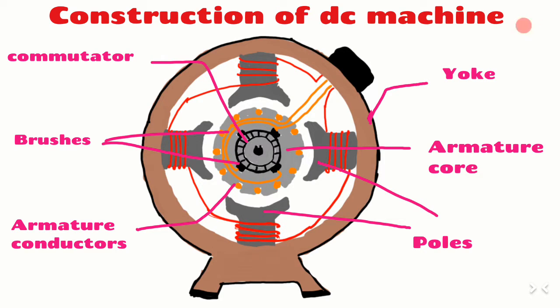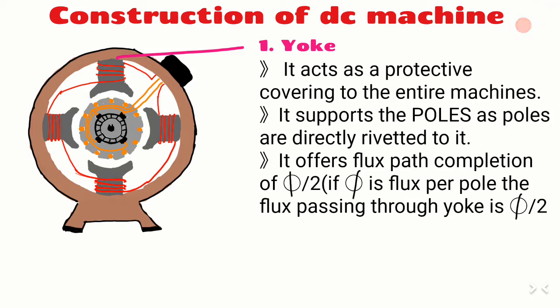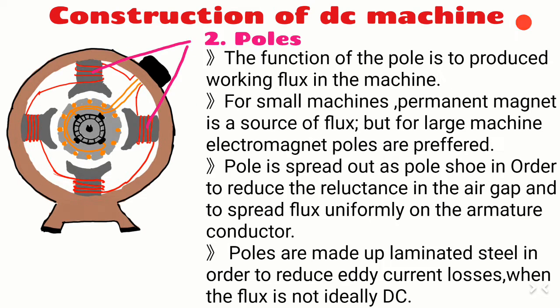The outermost part of the machine is the yoke. It acts as a protective covering to the entire machine and supports the poles, as the poles are directly bolted to it. It provides a path for flux. The flux passing through the yoke is phi divided by two, so the yoke should be of good magnetic material. For small machines we use a cast iron yoke, and for large machines we use fabricated steel.